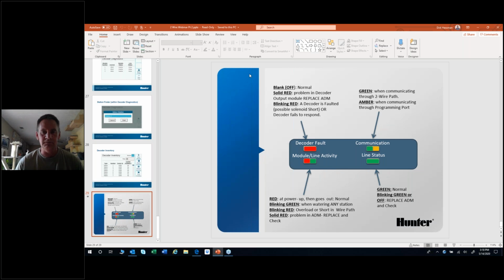On the decoder fault, if it's blank off, that's normal. You don't want to see any light there. If it's solid red, you've got a problem with the decoder output module, which is what the light is on, and you should probably replace that ADM. Blinking red means you've got a decoder that is faulted out there, or a decoder has not responded back to a command saying, hey, turn me on.